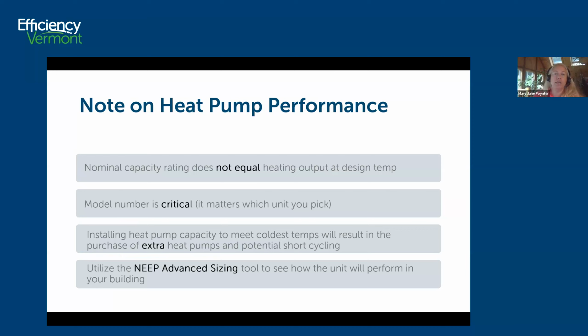Just a quick note on heat pump performance. So nominal capacity, if it's a 06 or an 09 or a 12, if it's a 12, that means it's rated for 12,000 BTUH. That typically is not the heating output, but the cooling output. The heating output at design conditions can be significantly lower. So that's important when you come to picking the model number. You need to look at the fine details and not just the number in the model number.